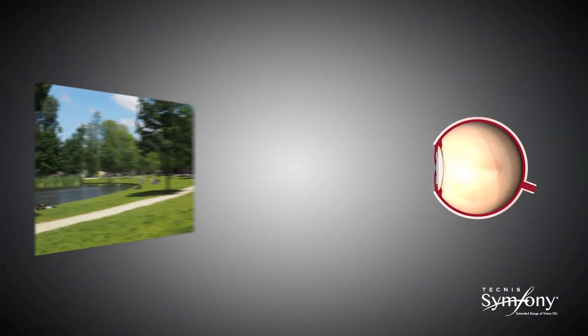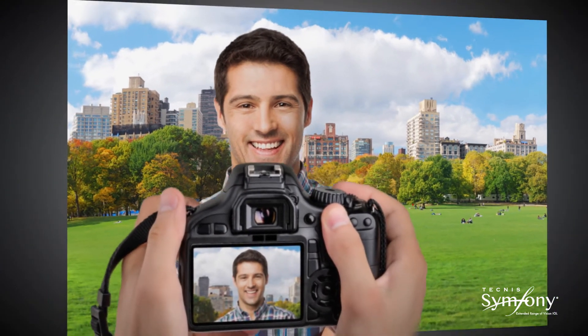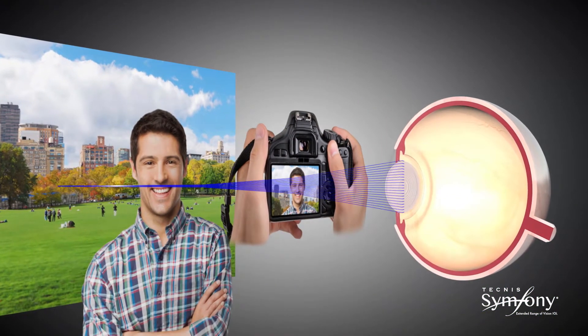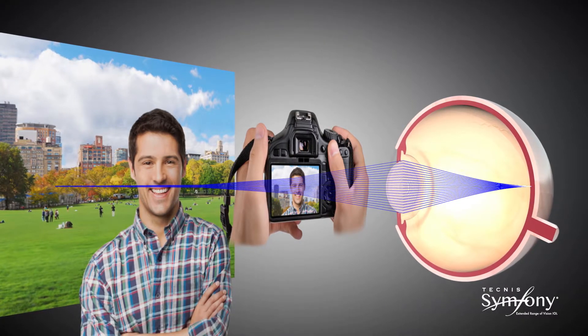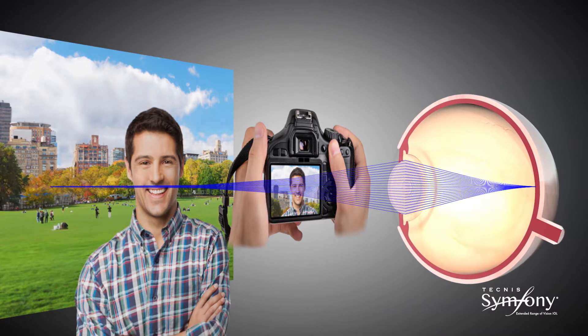In multifocal IOLs, diffractive technology transmits the light in such a way that it converges at more than one focal point. Tecnis Symfony's diffractive lens technology is optimized to transmit light over a range of distances. This is called constructive interference and results in an elongated focus.